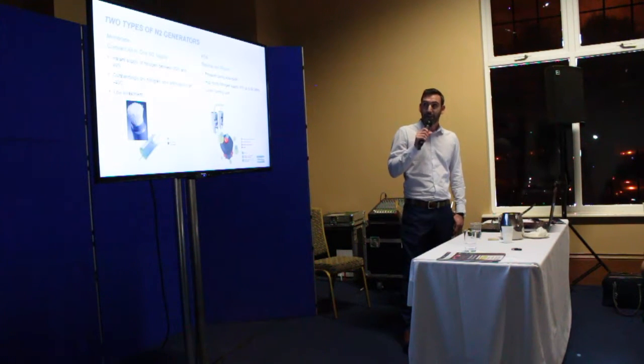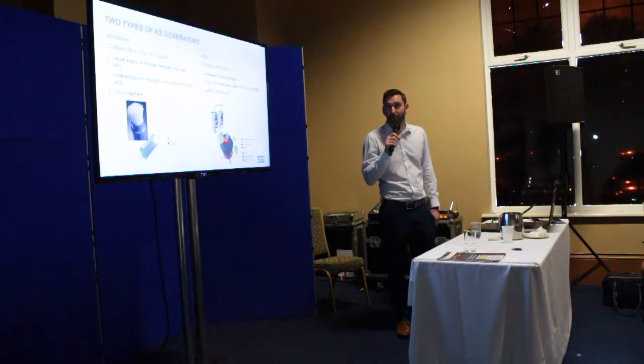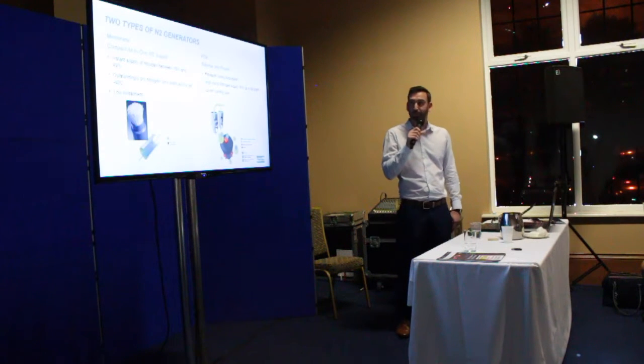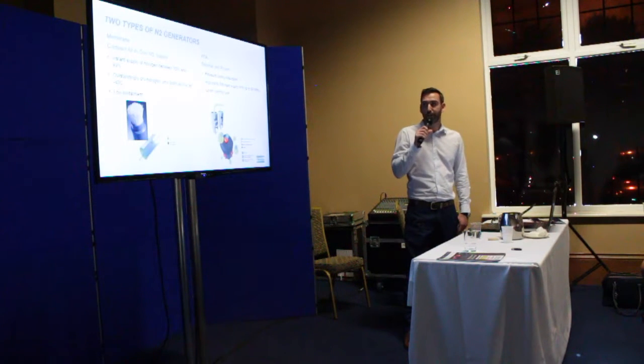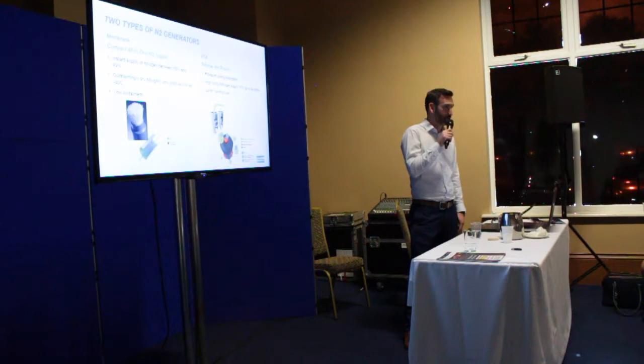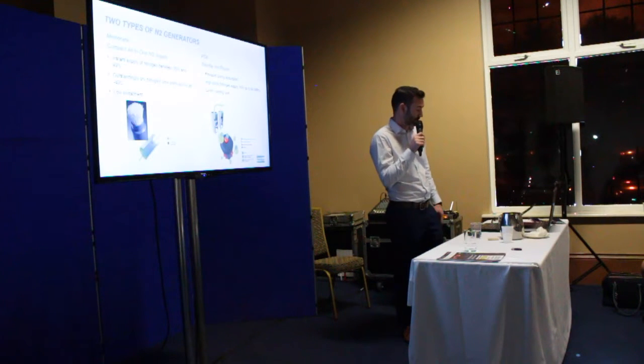The second is PSA technology. This also runs off a compressed air system. It's reliable and proven technology which uses pressure swing adsorption of a CMS, or carbon molecular sieve. It gives high purity nitrogen from supplies of 95% up to 99.999%. That is the same as your liquid nitrogen. The main thing about the PSA would be the low running costs.